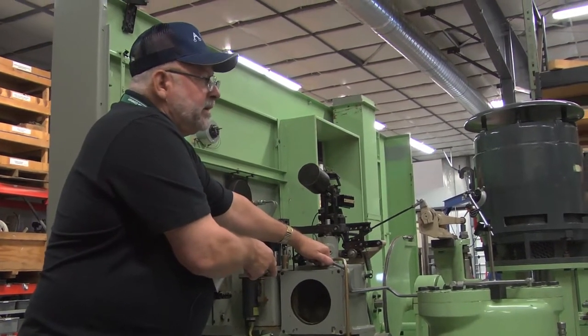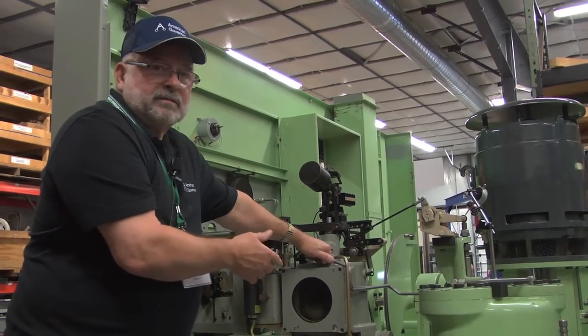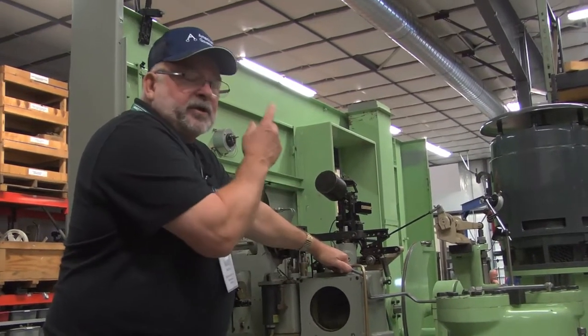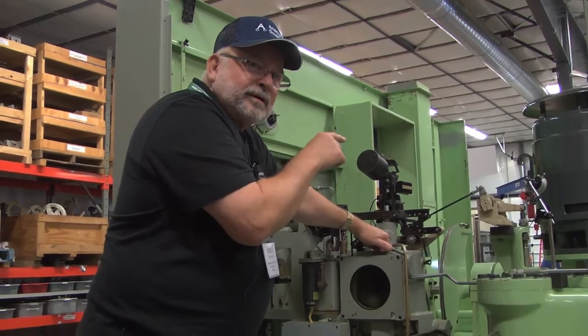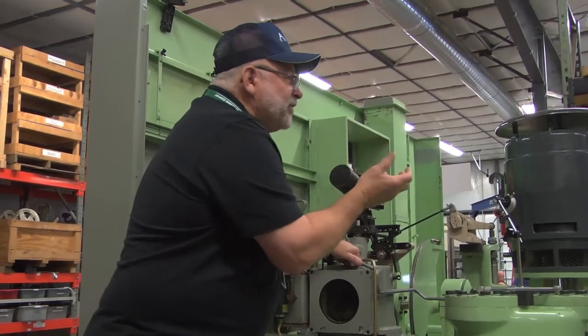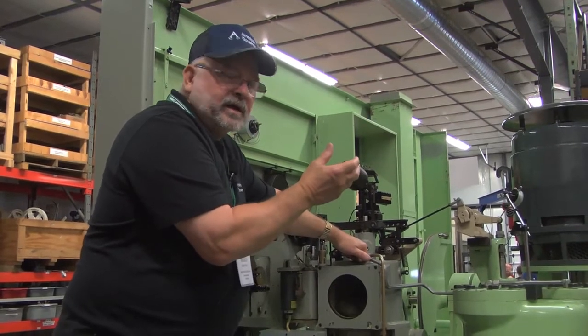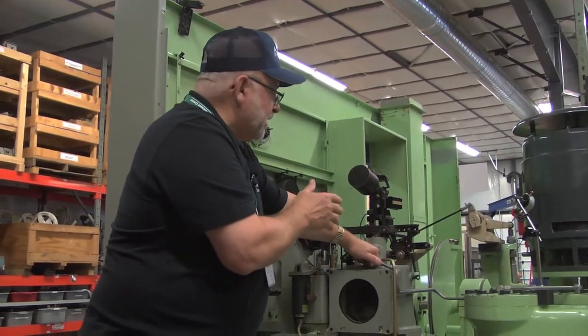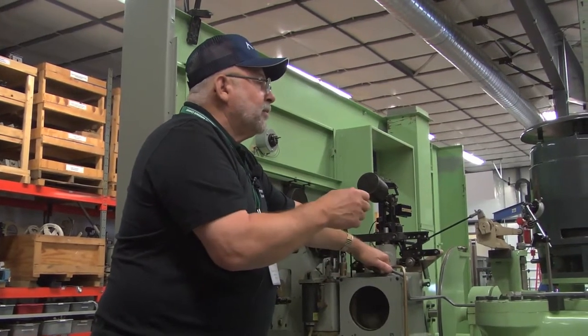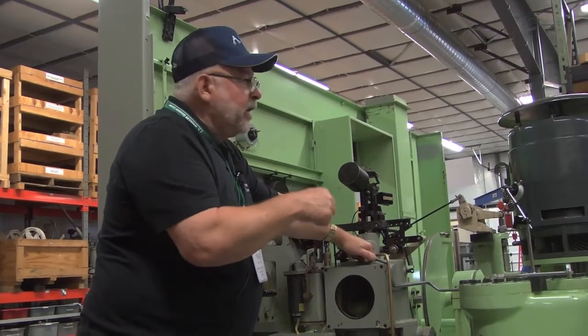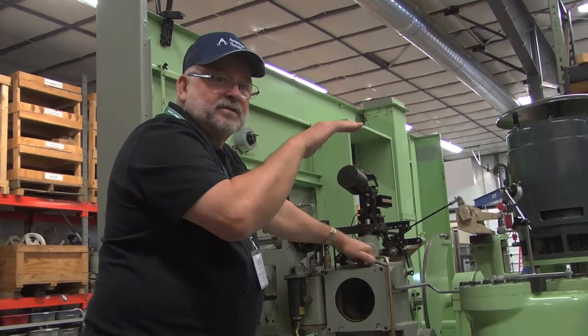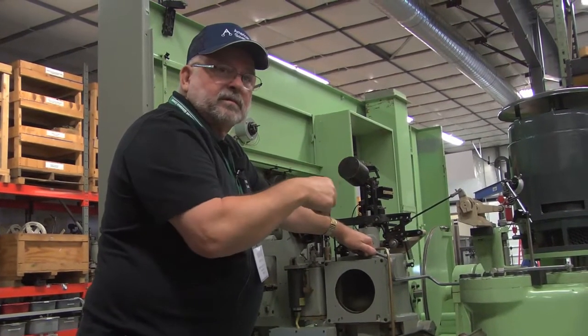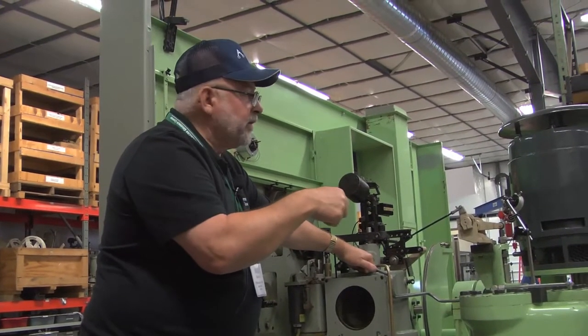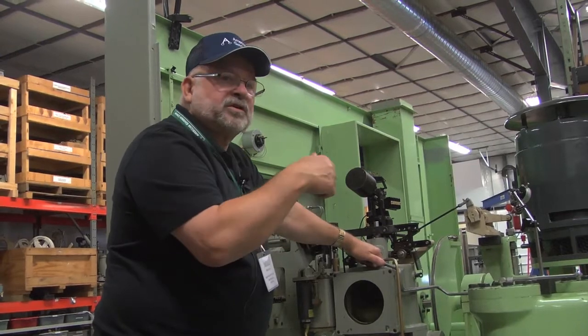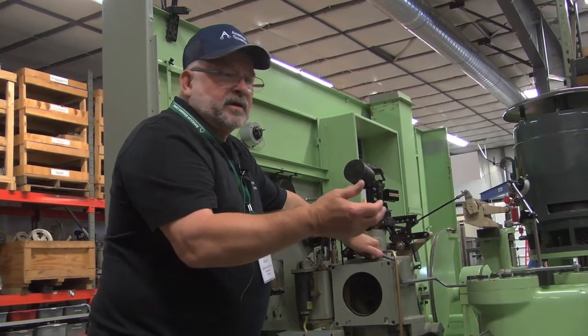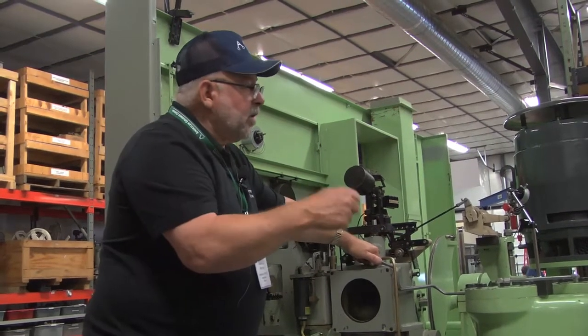What this does, if you had old bearings and they were starting to go bad, and your PMG started losing voltage, well then it can't drive through that rough spot on the bearings. So one of the biggest things on a Pelton that I always check every year, naturally on the PMG, I will go up with a 500 volt megger and make sure it's isolated with the insulation. Make sure it's isolated. You want plenty of megohms to clear there. You won't have any circulating current, so that's what saves your bearings in the PMG. The bearings will last a long time as long as you do that.